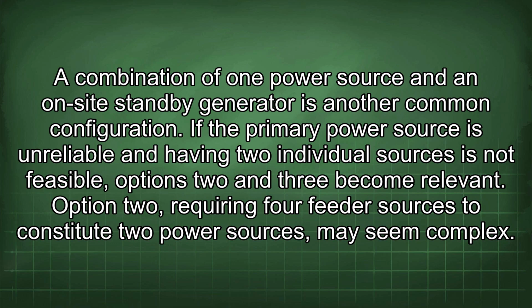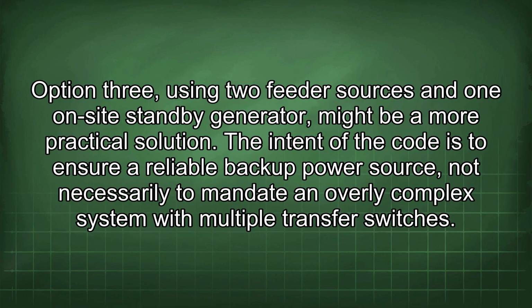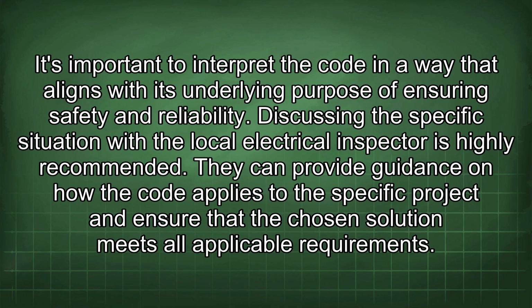If the primary power source is unreliable and having two individual sources is not feasible, options 2 and 3 become relevant. Option 2, requiring 4 feeder sources to constitute 2 power sources, may seem complex. Option 3, using 2 feeder sources and 1 on-site standby generator, might be a more practical solution. The intent of the code is to ensure a reliable backup power source, not necessarily to mandate an overly complex system with multiple transfer switches. It's important to interpret the code in a way that aligns with its underlying purpose of ensuring safety and reliability.